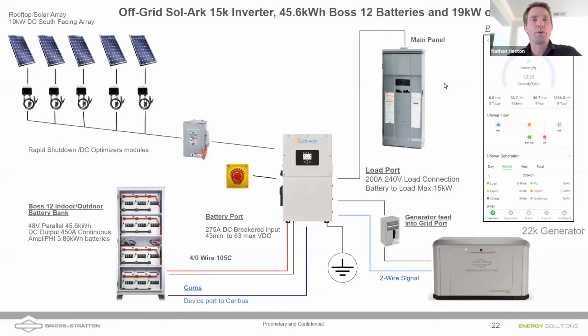Let's look at another example here. This is an example with an off-grid system. And in an off-grid system, you would not be utilizing the generator port. So John mentioned earlier that the gen port on the Sol-Ark is limited to 19 kilowatts. But in an off-grid situation, we would recommend that you use the grid port to bring in that generator. So you could bring in a 26K Power Protect Briggs & Stratton generator into that Sol-Ark 15K grid port.